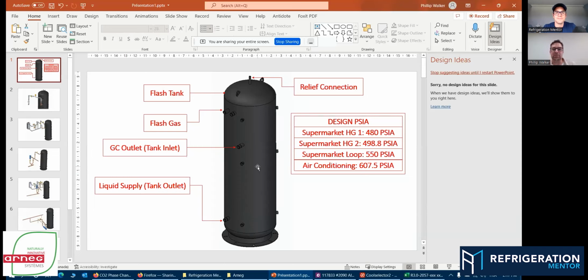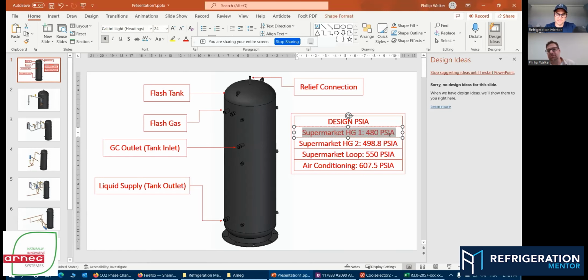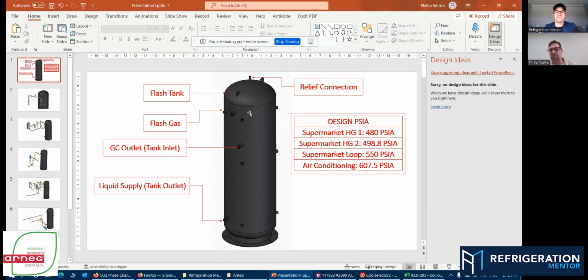And this is where we really get into different pressure ratings. How we go to market, and I think this is really important, is there's not one size fits all. And it's important to note, as you raise flash tank pressure here, you produce less flash gas because the difference across your thermal expansion or your high pressure expansion device is less. So when we're doing a standard supermarket with hot gas, this tank is running at about 480 PSIA. And this is when we're running evaporators that are standard. We're in a mechanical room, and evaporators are say lower, they're on a sales floor.